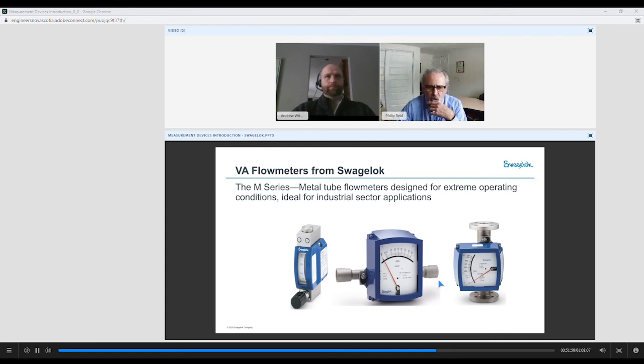These are metal flow meters. They have a metal tube, and they will use a spring and a magnetic interface. So these can be mounted horizontally, and we'll talk about that in a minute. But the metal tube flow meter is designed for extreme operating conditions. A lot of power plants, chemical plants, and refineries will use this type of flow meter. Also, it can be in a vertical or horizontal model.